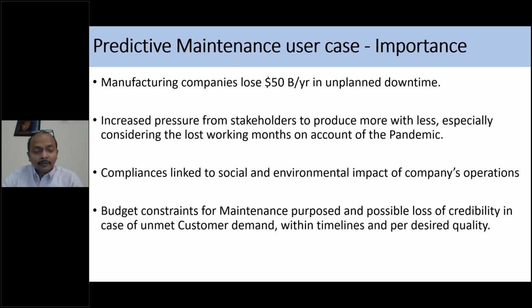All the time. So with technology like IoT, you'd be able to do this, because you can then start getting alerts that the temperature is not right, the bearing temperature is incorrect, or the motor current winding in one of the phases is high, or there is an unbalanced voltage or current, and all of these point to one or the other problem. So with a combination of these data points, you can then narrow down what is likely to happen, and plan your course of action.